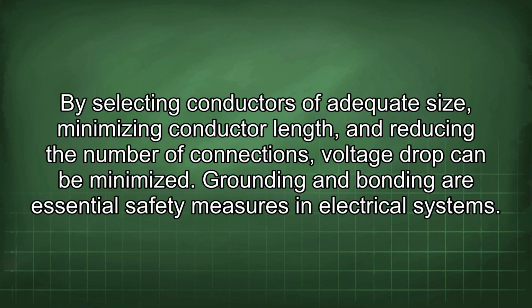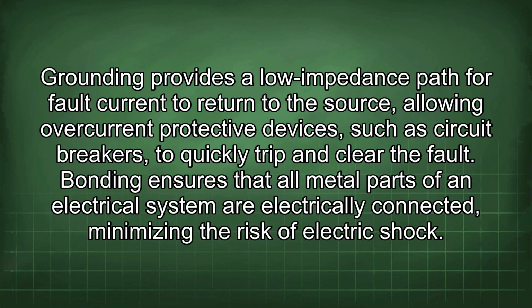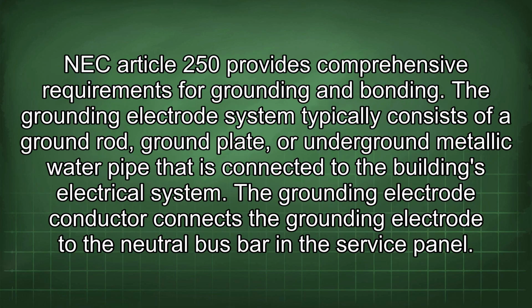Grounding and bonding are essential safety measures in electrical systems. Grounding provides a low impedance path for fault current to return to the source, allowing overcurrent protective devices, such as circuit breakers, to quickly trip and clear the fault. Bonding ensures that all metal parts of an electrical system are electrically connected, minimizing the risk of electric shock. NEC Article 250 provides comprehensive requirements for grounding and bonding.